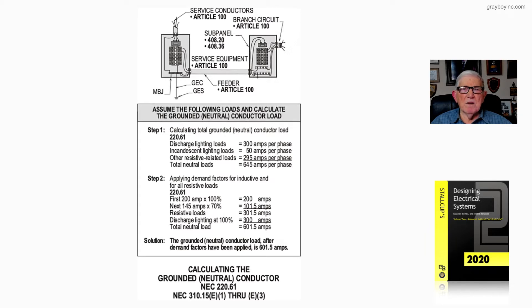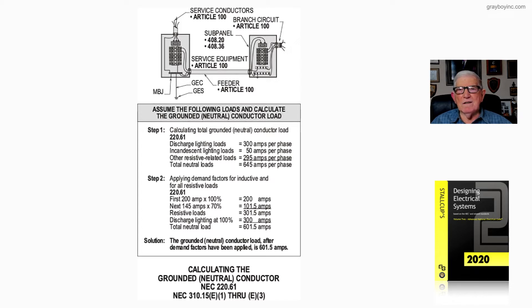Since this is a sub-panel — we call it a sub-panel because it's a sub to the service — it's Articles 408.20 and 408.36 that you have to review. But to isolate the neutral and bond the grounded bar to the panel, go to 408.40.